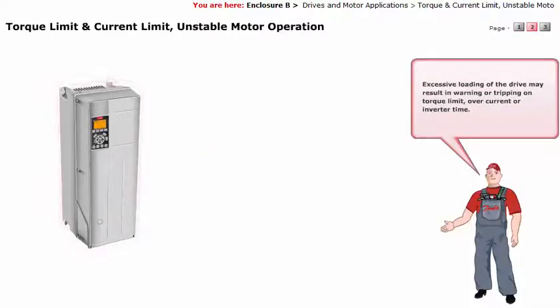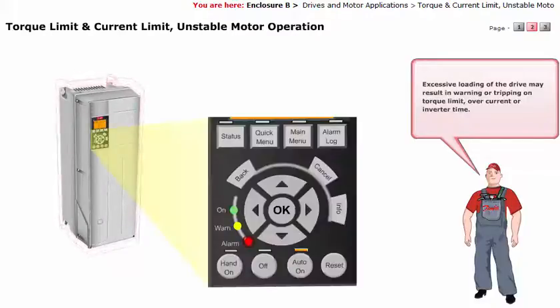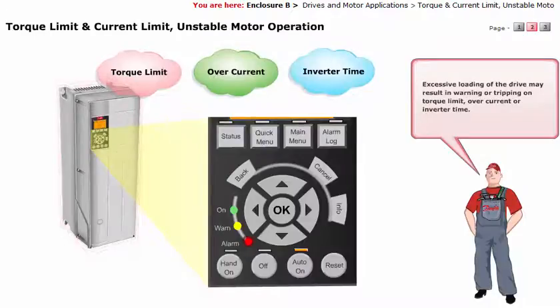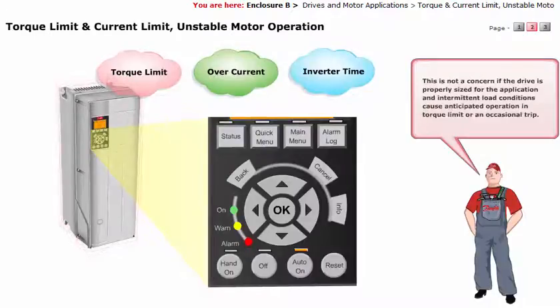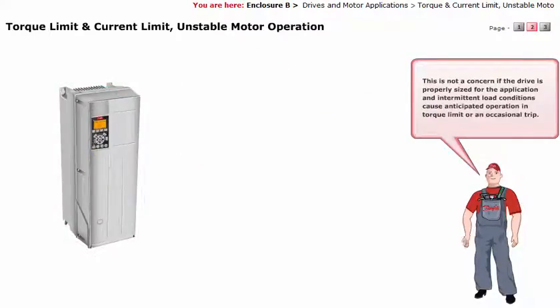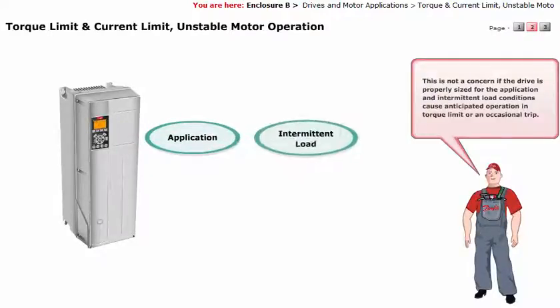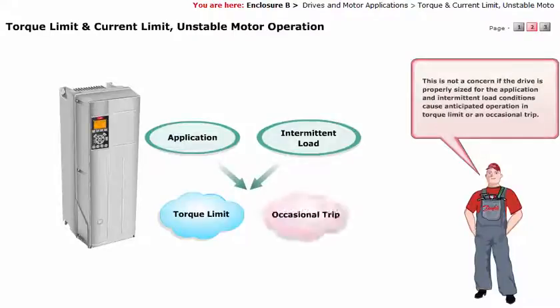Excessive loading of the drive may result in warning or tripping on torque limit, over current, or inverter time. This is not a concern if the drive is properly sized for the application, and intermittent load conditions cause anticipated operation in torque limit or an occasional trip.